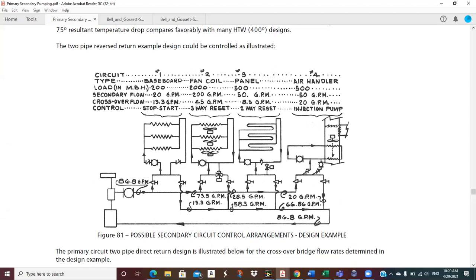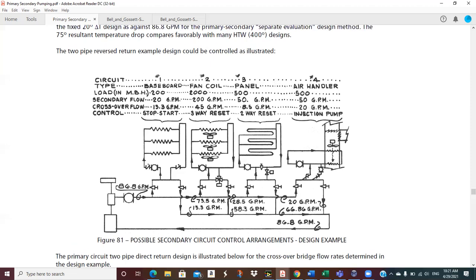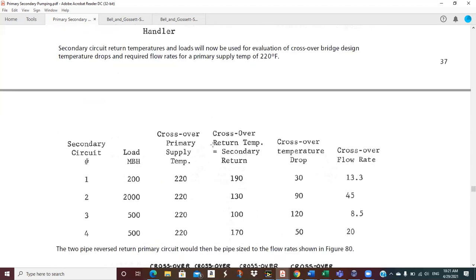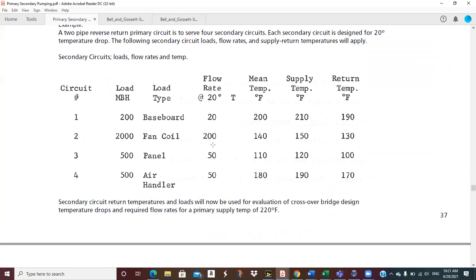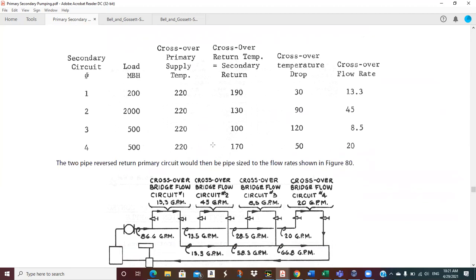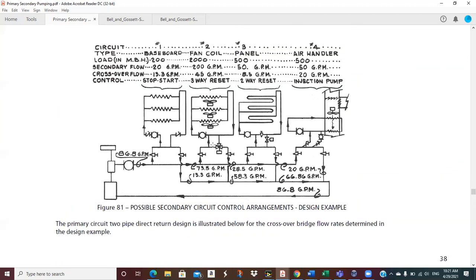And you can see the mix, so 45, so what do we got? 155 GPM bypassing that's mixing right here with this 45 GPM of crossover flow to get us, what was that? I forget the temperature. What was the temperature in that second? That one knocked it way down, didn't it? Yeah, we're mixing to 150 in that secondary. So we'll have 150-degree water here going out through all of these.